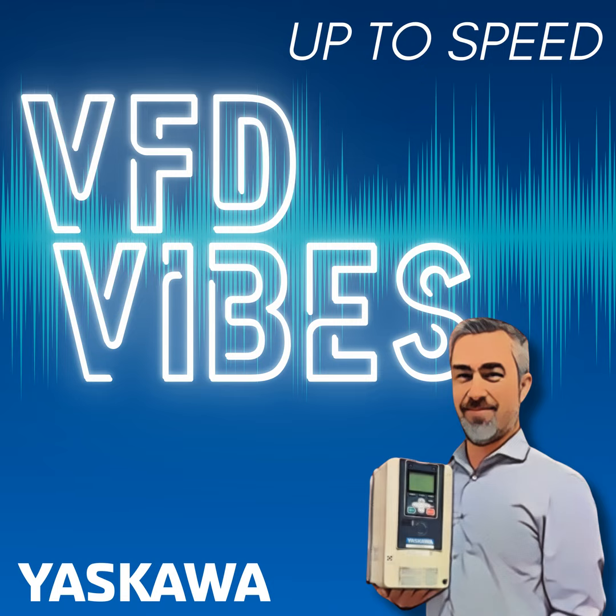The common spec out there in the industry is IEEE 519. And if you meet or don't meet that, and if you don't meet it, then that's where you may need to have a different type of VFD, such as the Yaskawa matrix drive, or you may want to purchase line reactors or filters to help mitigate some of those harmonics from getting back onto the power line. And this tool helps you understand if you pass or fail, and then you can add in these components via the tool to get to a point where, okay, it looks like we meet this standard.